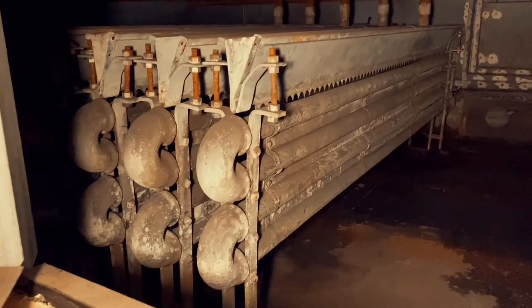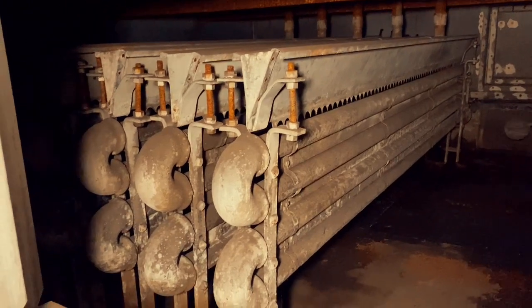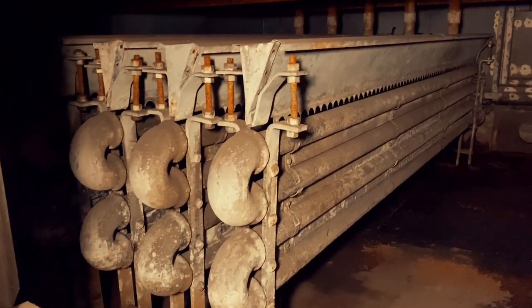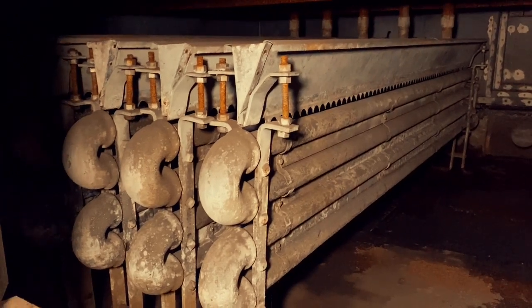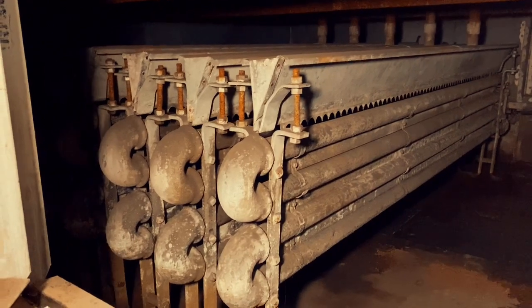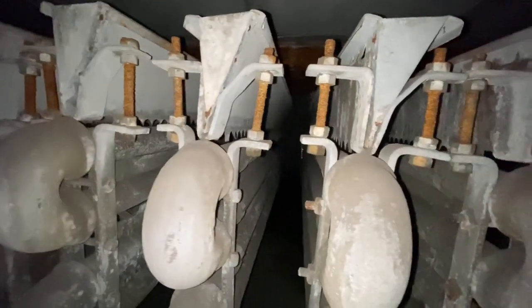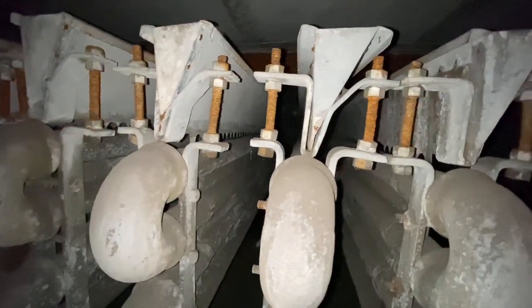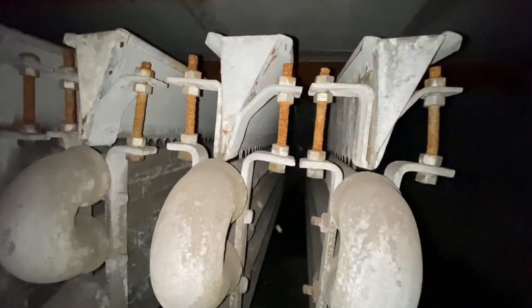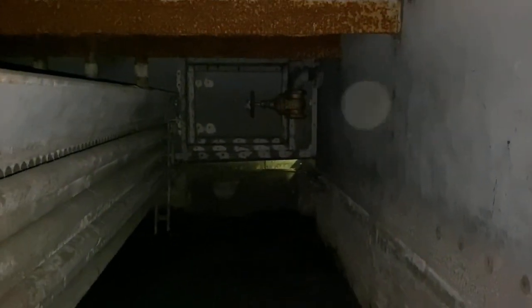Yes, there you go. So all that water that was sprayed above what you're looking at now, we don't want all that water in it as it goes through the house. So there are baffles between those coils that you can see in front of you, and then that water is reclaimed in the baffles, comes back into this tank, and this is the recirculating tank, which can be continually chilled by the brine system, giving us air-conditioned air to send out.